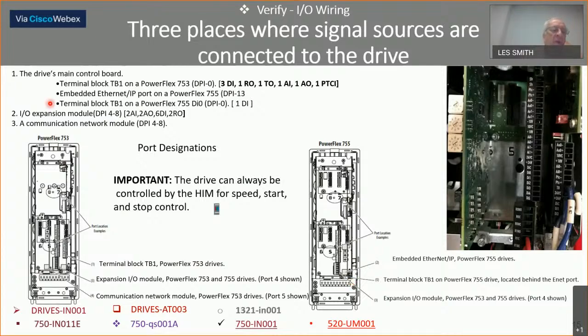Then we have I/O cards that we can add. We have 3 to 5 slots that can have different I/Os in them: encoders, digital I/O, COM cards. And here's the COM card that can be added to either one if you wanted to have dual COM cards on the 755. But being aware of where that's at, the drive can always be run from the HIM without having any wires run to it, just for testing purposes. And here's indications on where things are at.